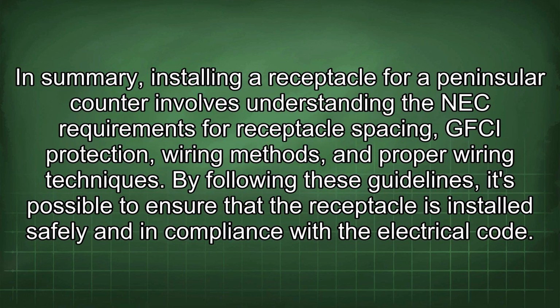In summary, installing a receptacle for a peninsular counter involves understanding the NEC requirements for receptacle spacing, GFCI protection, wiring methods, and proper wiring techniques. By following these guidelines, it's possible to ensure that the receptacle is installed safely and in compliance with the electrical code.